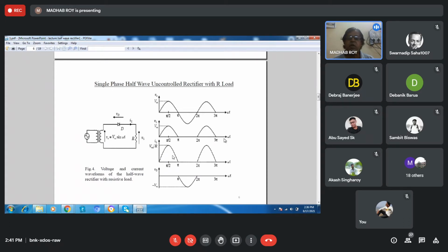That means a unidirectional current is going into the transformer, and this unidirectional current will be reflected into the primary side. The magnetizing current will be combined with that, and thus it will form saturation, because there will not be demagnetizing current, only magnetizing current.